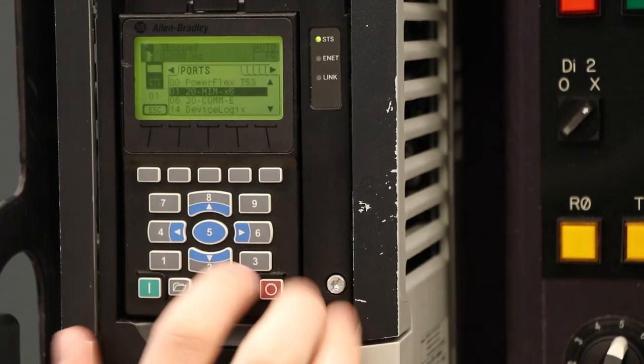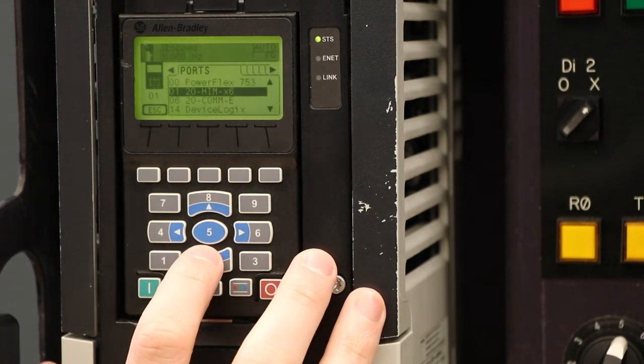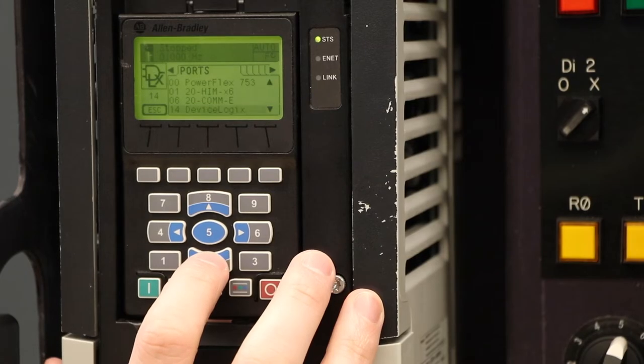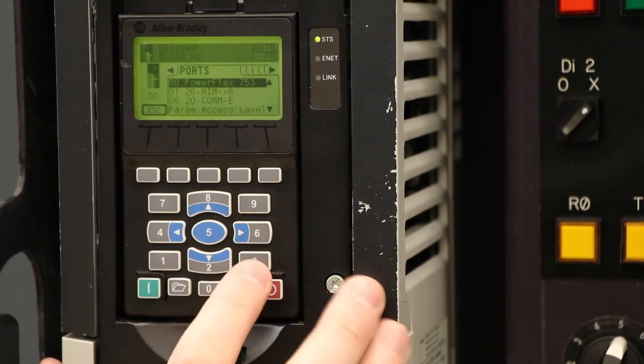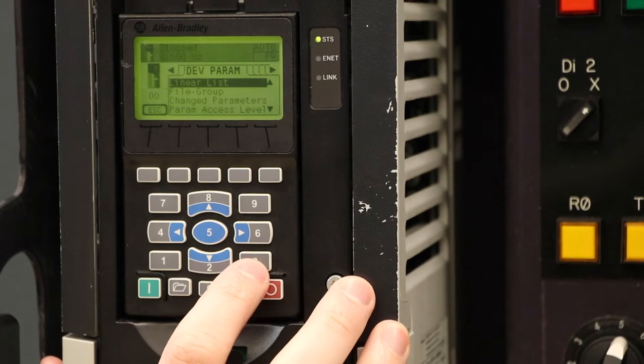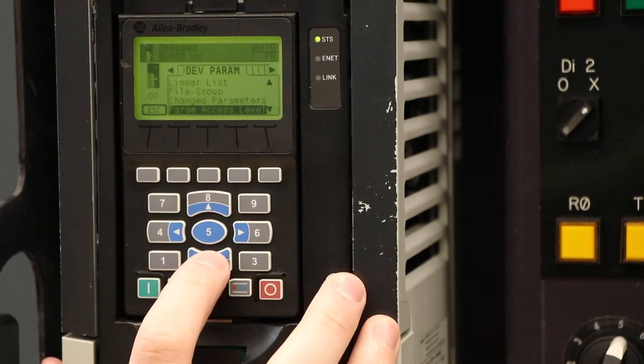From here, we've got our port zero PowerFlex drive — that's our main control board. Port one is our HIM module on the front of the drive. Port six is the ethernet card installed in our drive, and port 14 is the embedded DeviceLogix. We're going to stay on port zero, our PowerFlex 753, and move over to the next folder using the six button. From here, we've got all of our PowerFlex drive parameters: linear list, file group, change parameter, and parameter access level.